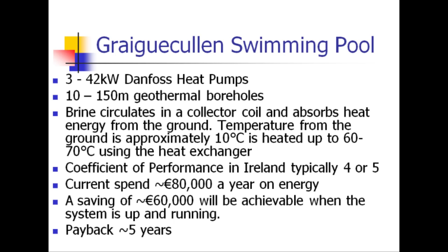The geothermal system has 4 42-kilowatt heat pumps and 10 150-metre geothermal boreholes. The temperature we're getting out of the ground is approximately 10 degrees, and it's heated up to between 60 and 70 using a heat exchanger.